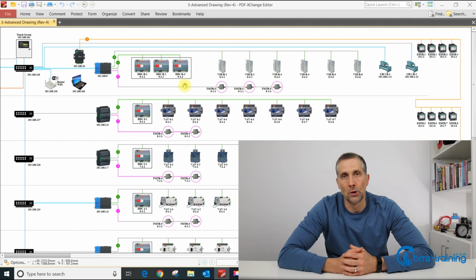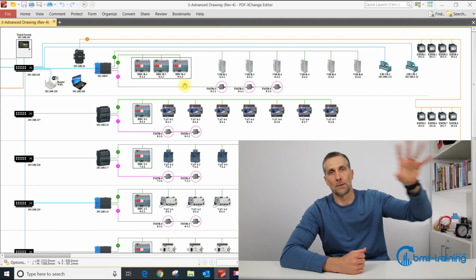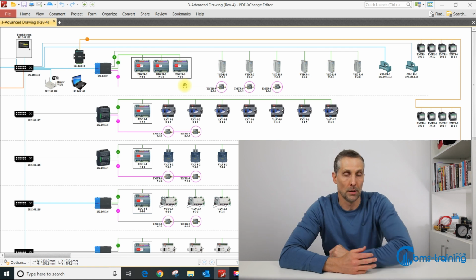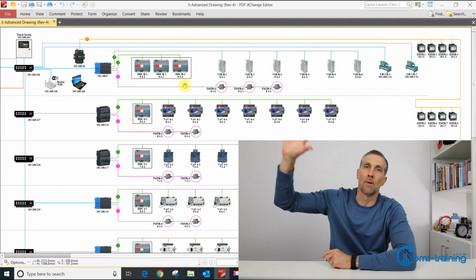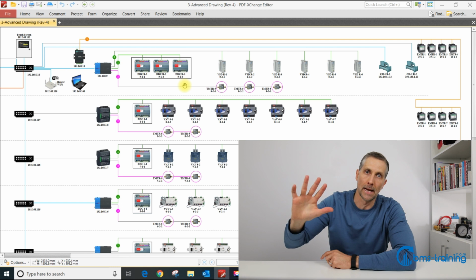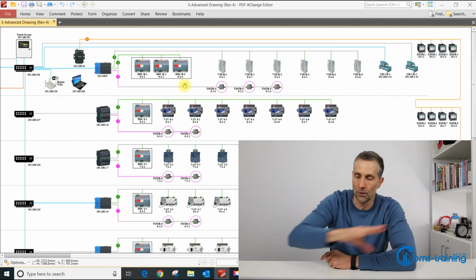And the building analytics package could be checking things from the BMS controllers, getting things from the VSDs, getting things from the electric meters as well. So we have multiple supervisory devices accessing data through the Ethernet and onto the subnetworks. Now, if you have a small project, and on the roof you have 2 electric meters, you've got 2 VSDs and 2 BMS controllers, it's a small job, it's a $200,000 job. Of course, you're not going to separate those devices.